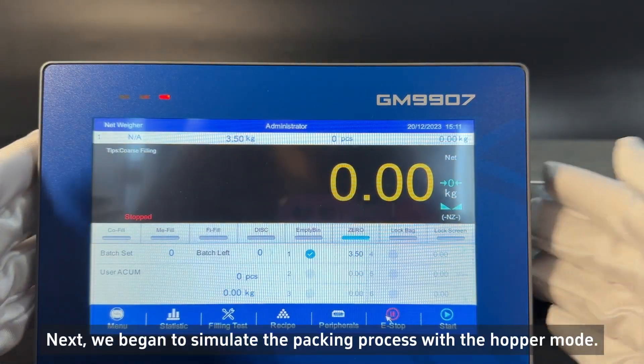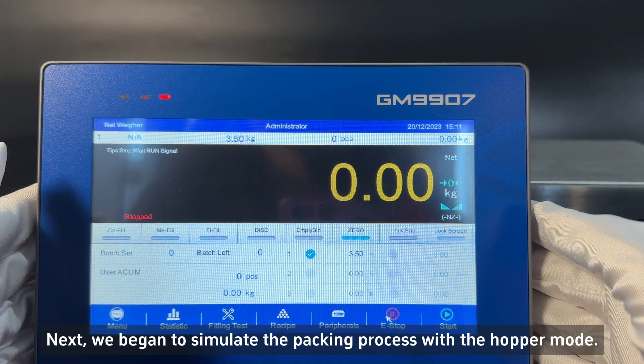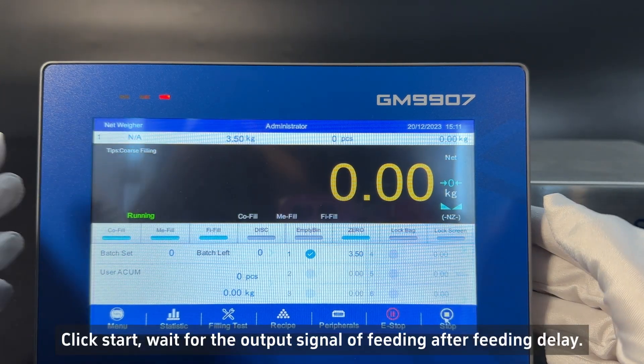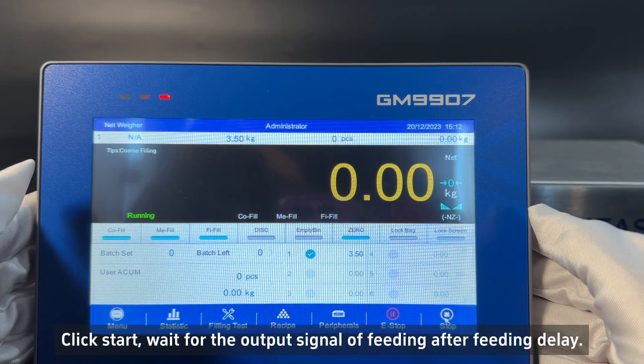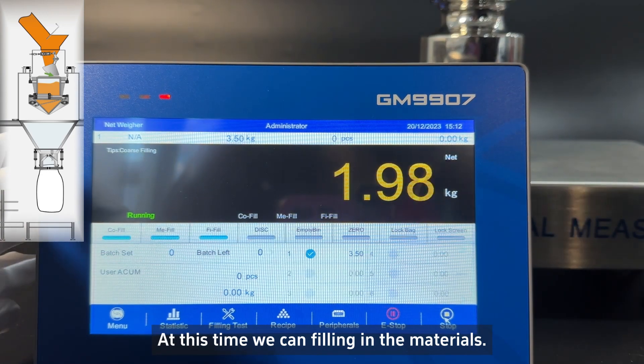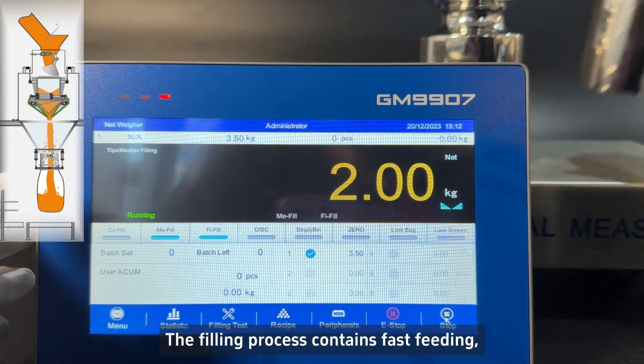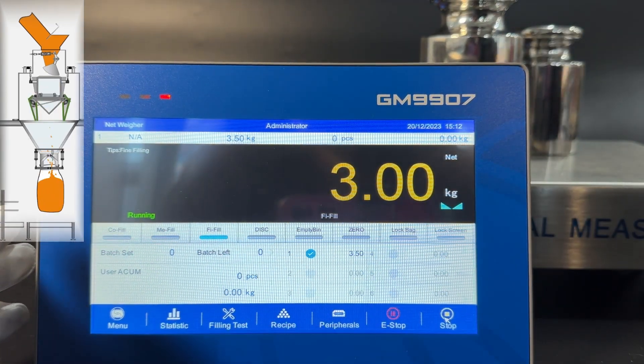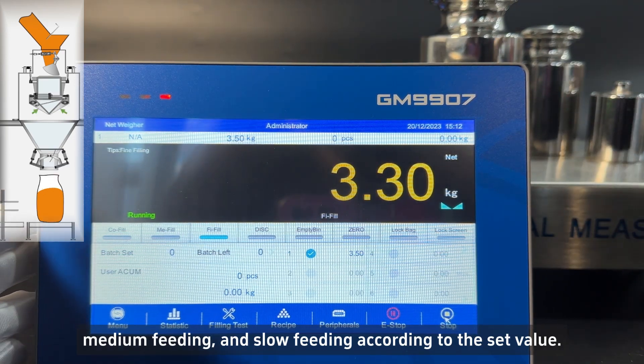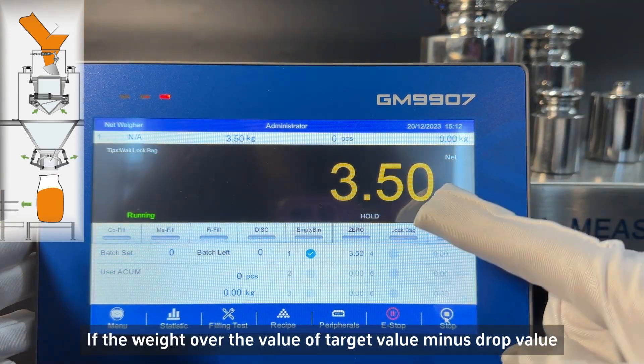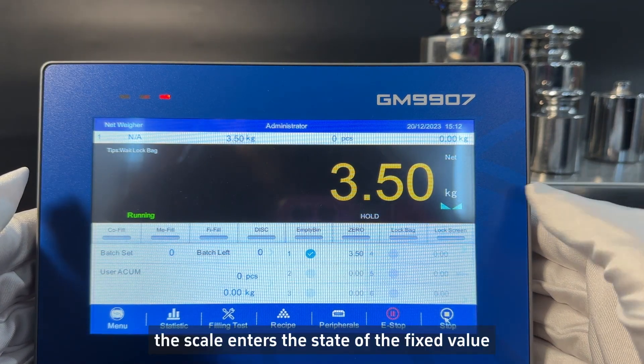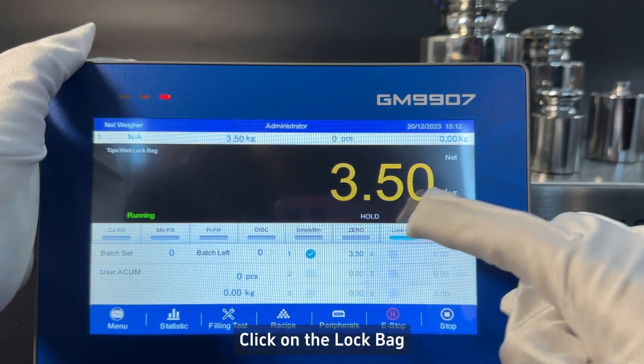Next, we begin to simulate the packing process with the hopper mode. Click start and wait for the output signal of feeding after the feeding delay. At this time we can fill in the materials. The filling process contains fast feeding, medium feeding, and slow feeding according to the set value. If the weight exceeds the value of target value minus drop value, the scale enters the state of fixed value — click on the lock bag.